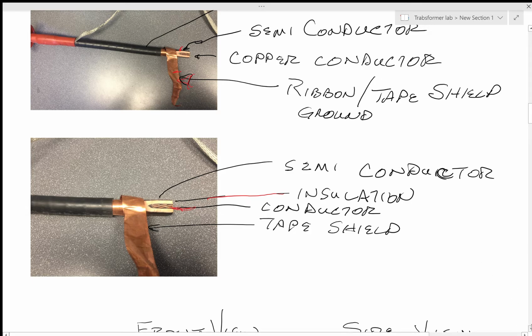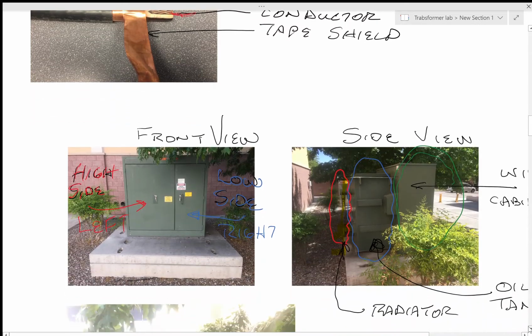So that's the type of connectors you can have on a 5 kV system or a 25 kV system. You can have elbows on the 5 kV system. You can have terminators on the 25 kV system. So, this is just to show you how we terminate this stuff here on campus. So the next thing we have is a transformer lab. So you have the front view and the side view of the transformer. The front view, the high side is always on the left side, always on the left side. And the low side cabinet is always on the right side.